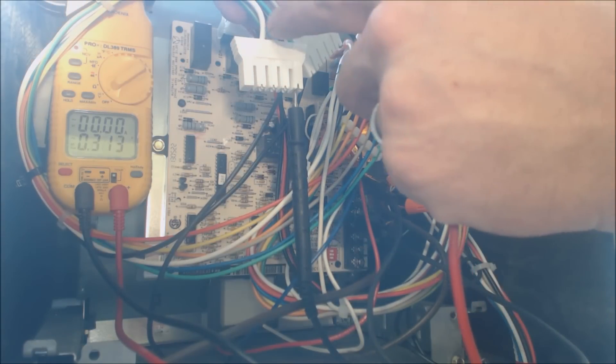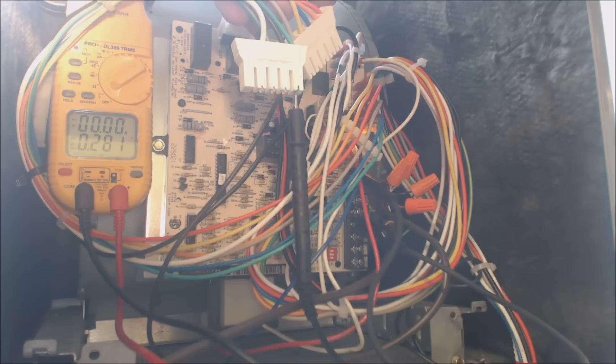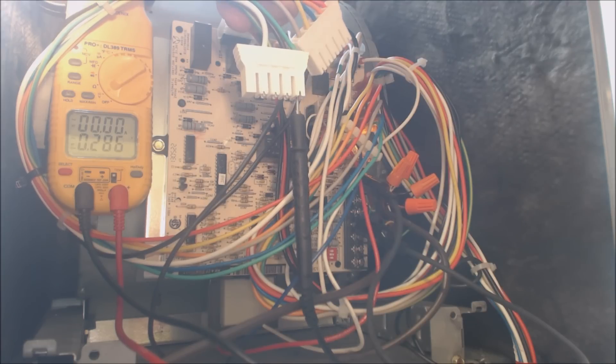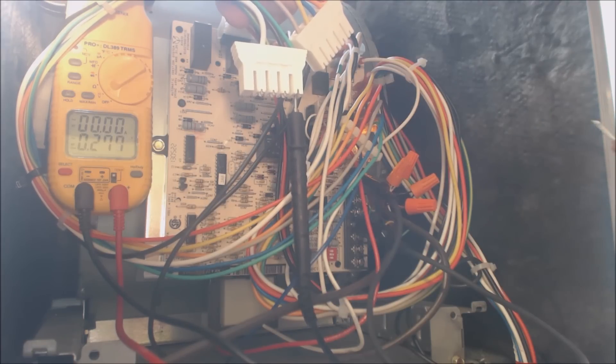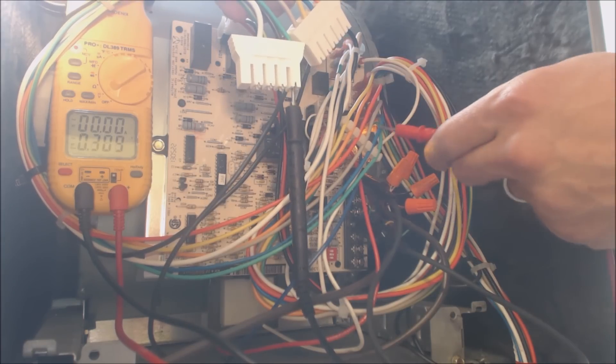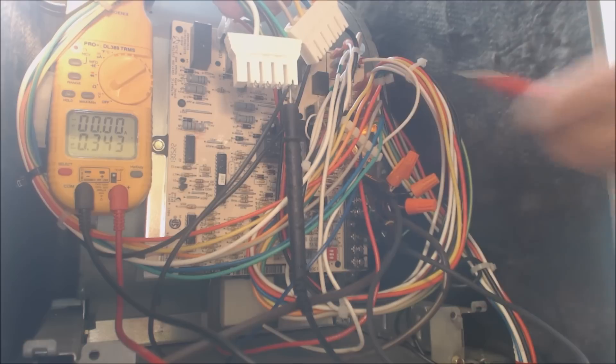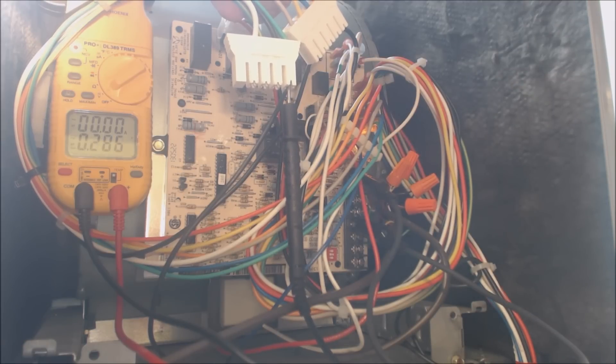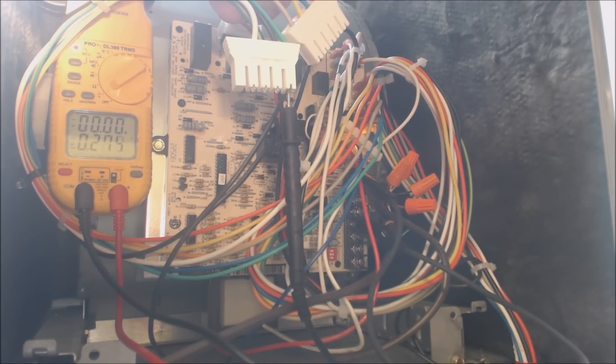So what we have here is we have one probe into the common for the 24 volts. We know that the white and black are hot. We already tested them. And now we're just going to see which one of these wires that the control board is sending power to the blower motor with.